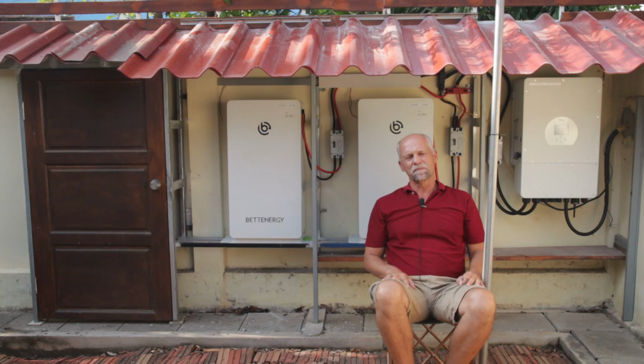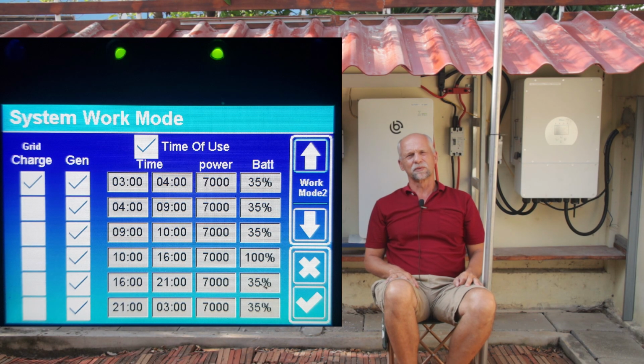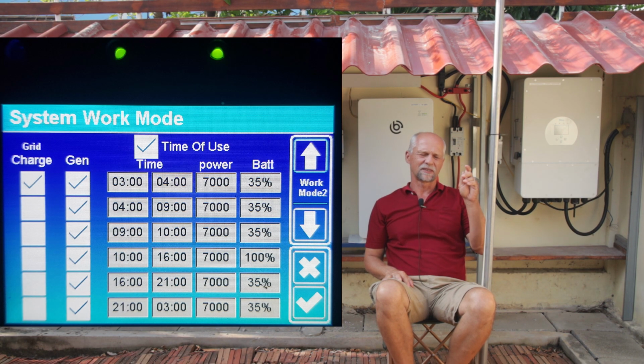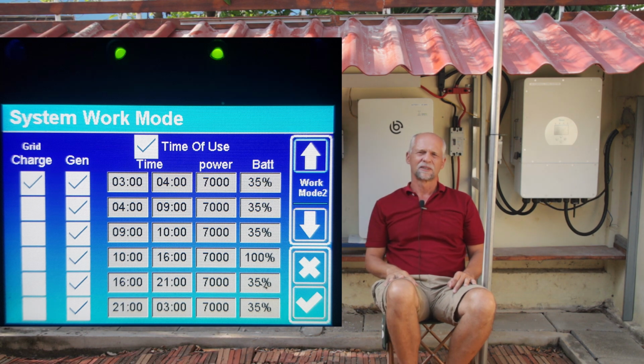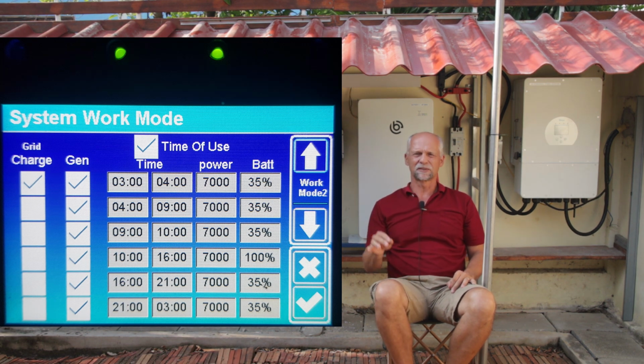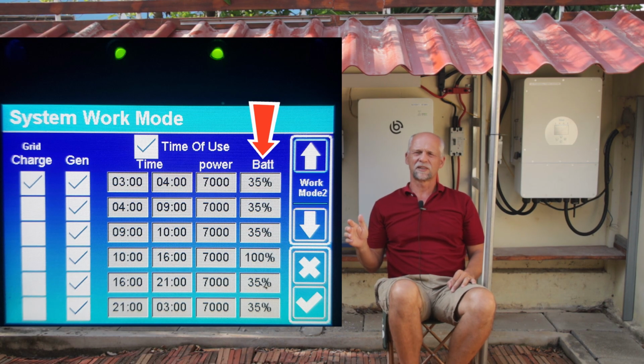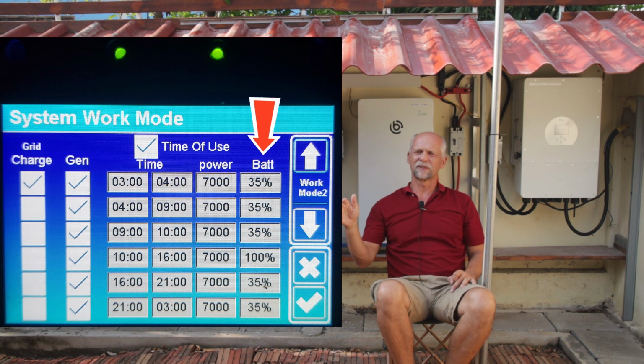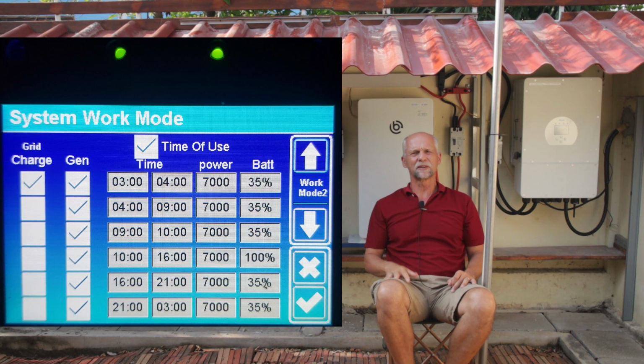For that, you have to make sure your battery actually gets charged up. If your battery strategy in the time-of-use table just keeps the target state of charge low and waits for excess energy to charge the battery, but when there's no excess the battery is discharged again right away, then at the end of the day you never reach a full state of charge — and that day, you also wouldn't have balanced.